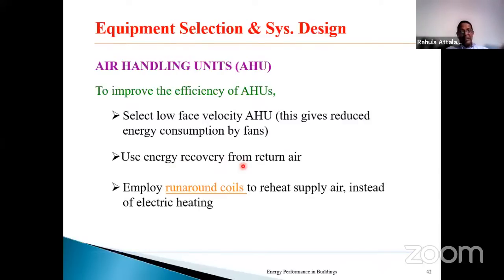We have different mechanisms: a thermal wheel, a heat exchanger, run around coils, etc. Rather than sending the cold used air directly to the atmosphere, make use of some heat recovery method to transfer part of that coldness into the incoming air, thereby improving the energy performance of the air conditioning system.